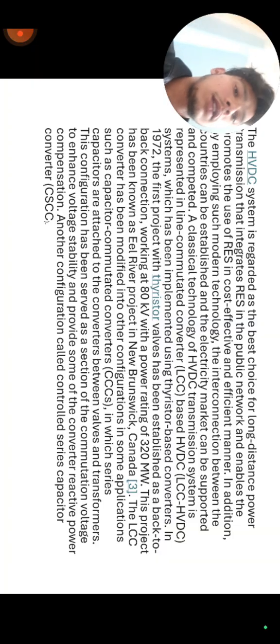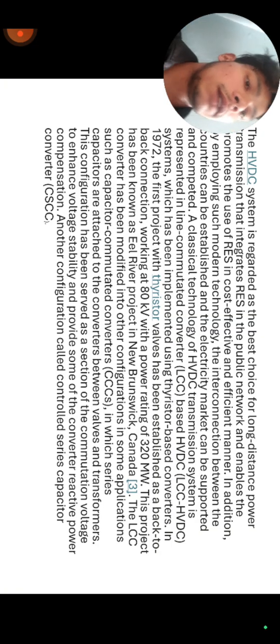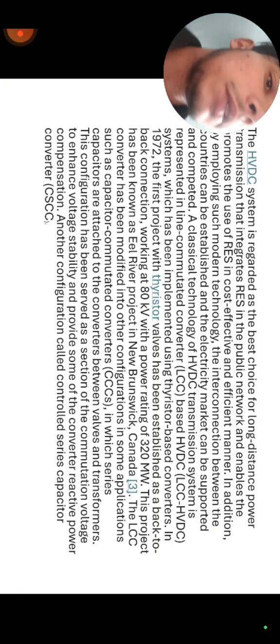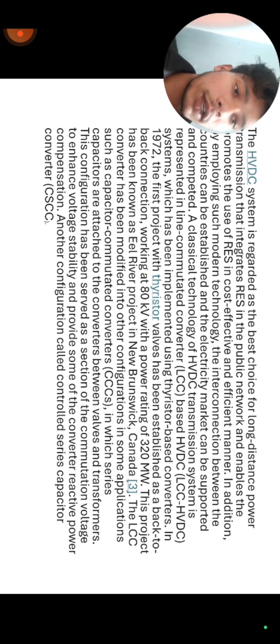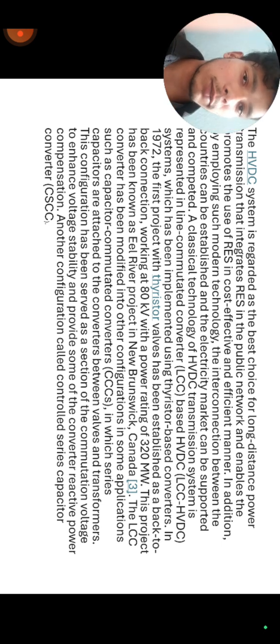In some applications, such as capacitor commutated converters, series capacitors are attached to the converters between valves and transformers. This configuration serves as a source of commutation voltage to enhance voltage stability and provide some of the converter reactive power compensation.